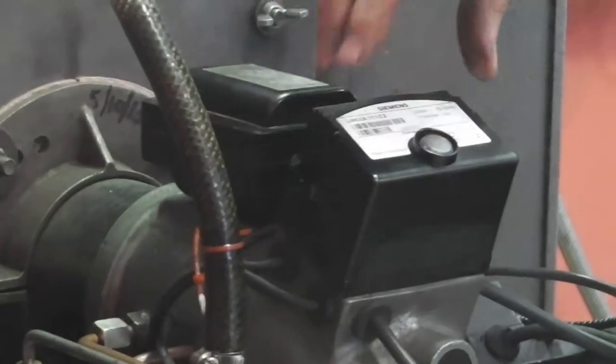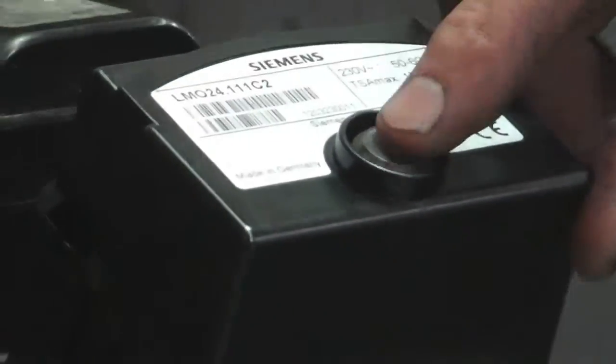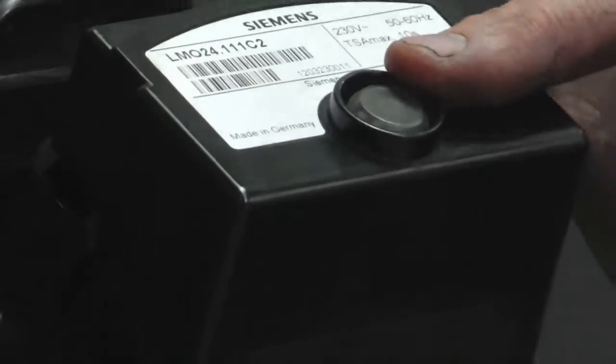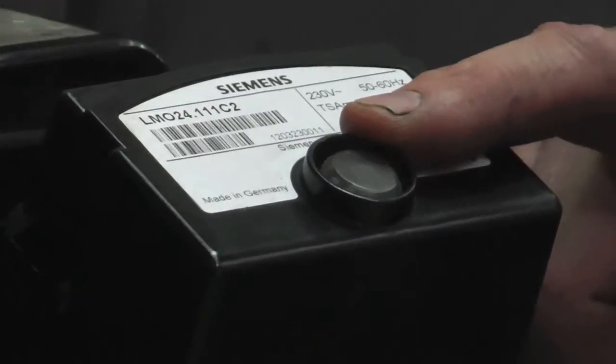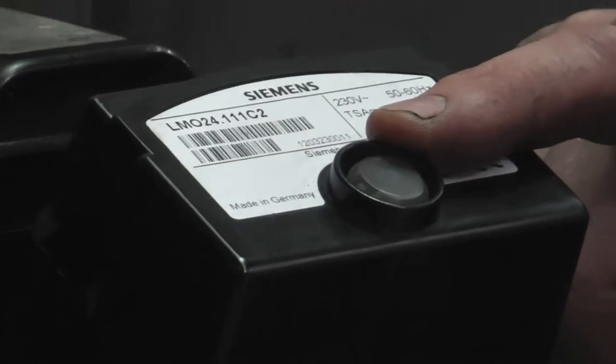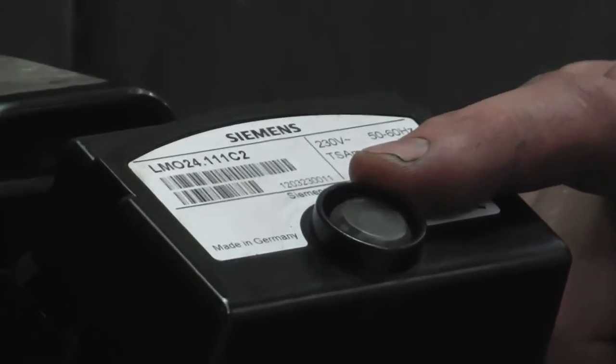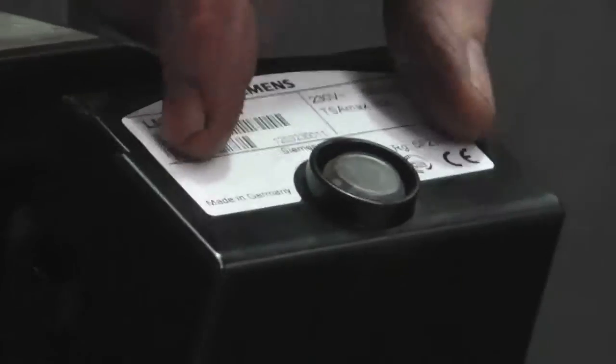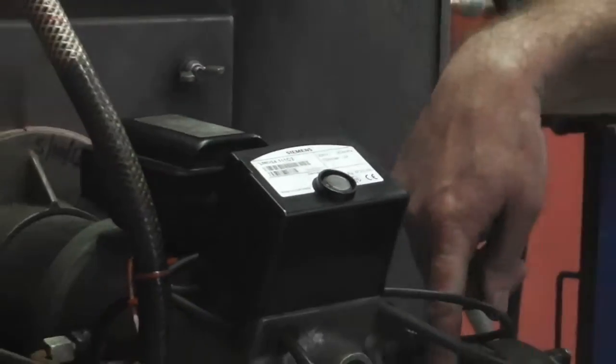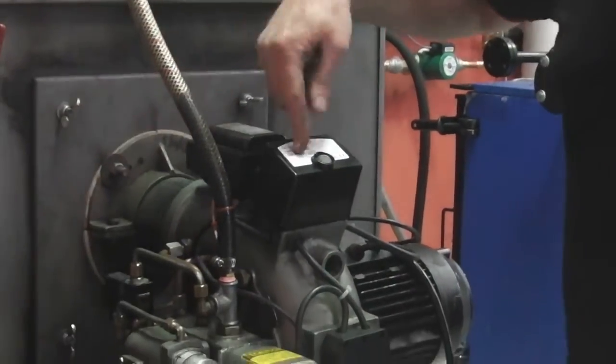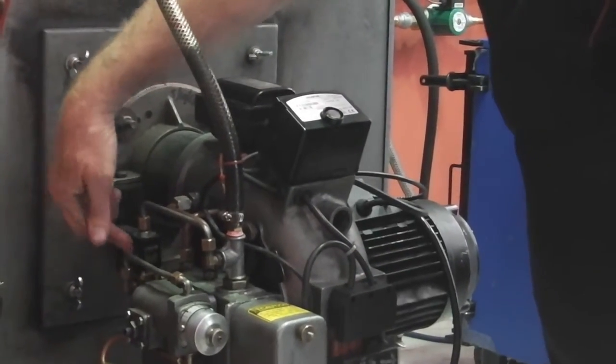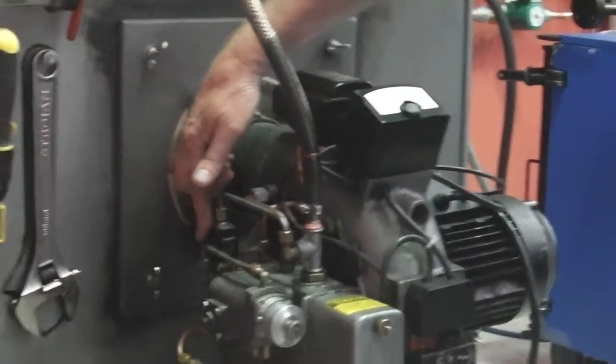This guy here is the brain of the controller. It's got a button here that's called a flame failure button. If that button turns red, then the burner gun has failed an ignition and has gone out for safety reasons. This controller manages the ignition, the electric motor, and something we haven't talked about yet, is this solenoid valve over here. This solenoid valve normally opens up after about five to ten seconds, once the motor starts.